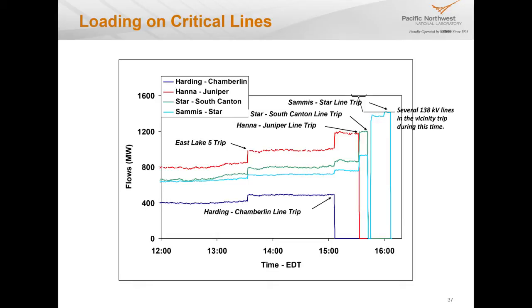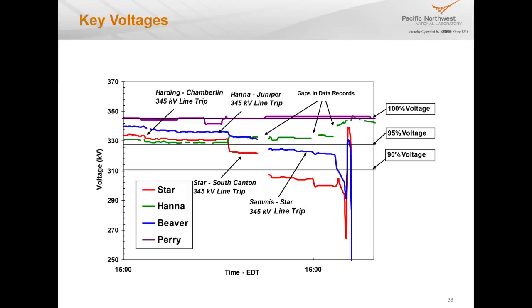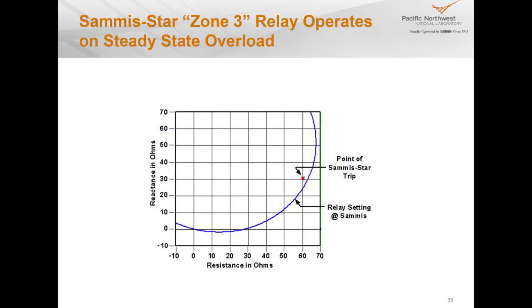And then when you start losing the lines, so this is the first one, that power has to be picked up by the other lines, right? And so then you lose that one, and they go up to there, and so on and so forth. So it's kind of a domino effect, but it really was the Sammis-Star line that tripped due to protective relay action. And this is what the voltage was doing the whole time. 90% nominal on the transmission line is considered very low. That's the relay setting point at which it tripped.